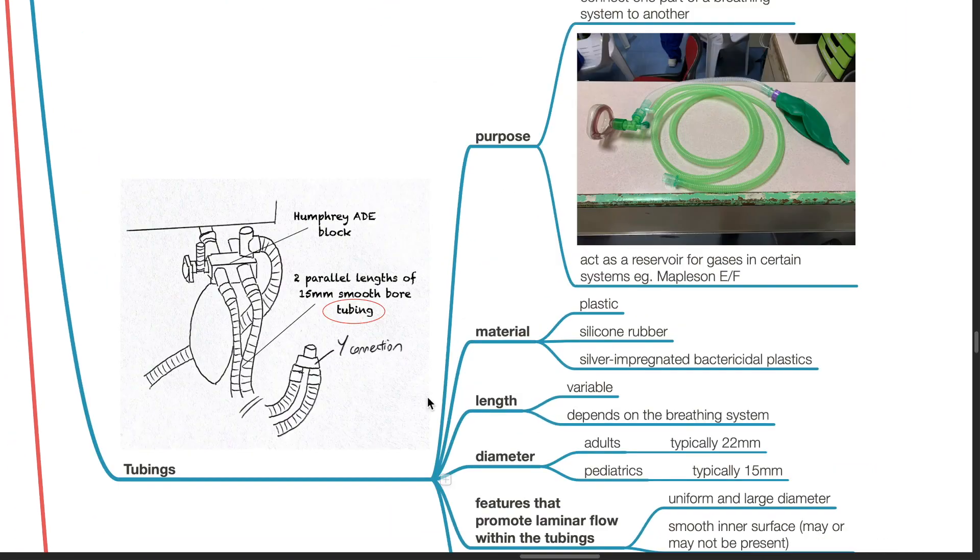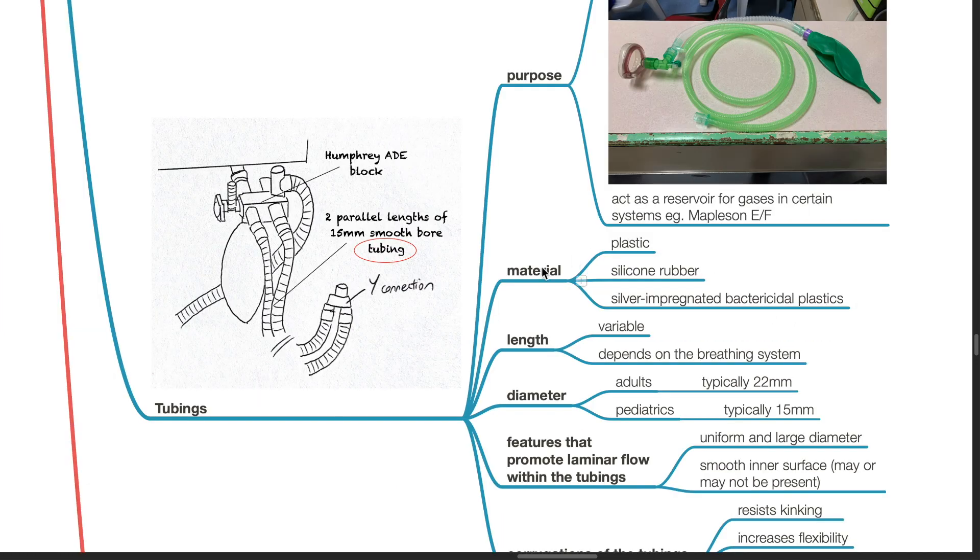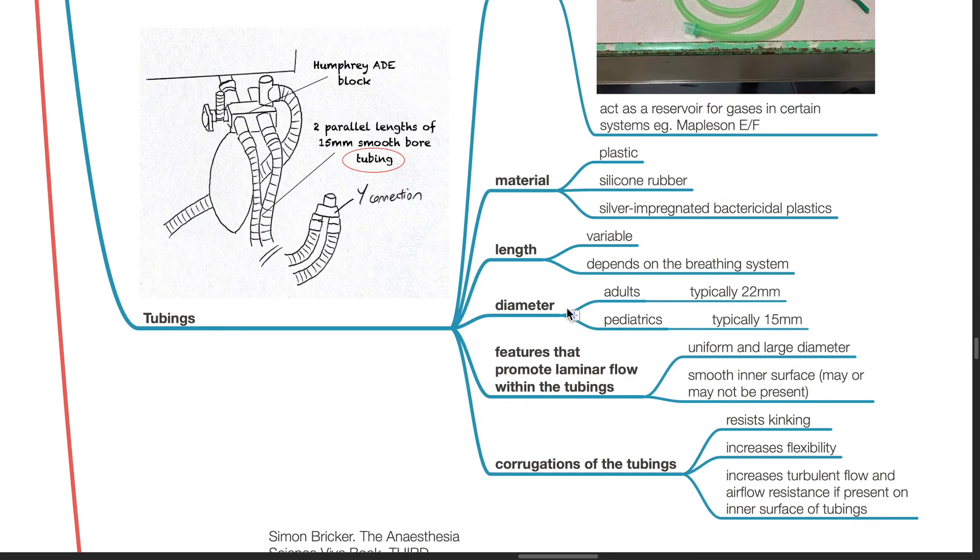Tubings. They connect one part of a breathing system to another and act as a reservoir for gases in certain systems such as the Mapleson E or F system. It is made of plastic silicone rubber or silver impregnated bactericidal plastics. The length is variable and depends on the breathing system. The typical adult diameter is 22 mm and for pediatrics it is typically 15 mm.